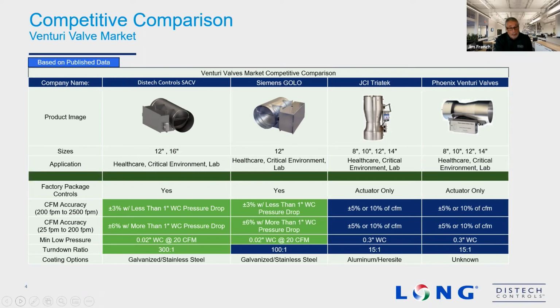The GOLO is the predecessor in technology to the smart air control valve. Previous technologies, again, limited in turndown, their turndown ratio 15-to-1. They advertise a 0.3-inch inlet pressure minimum. However, most of these valves require at least an inch of pressure across the valve to get it to accurately perform. And what we're talking about here is all the way down to 0.02 inches on the high accuracy version of our valve we're going to be releasing here over the next few months to address the lab and the healthcare space. How we're able to do this is through what's called variable orifice plate technology.